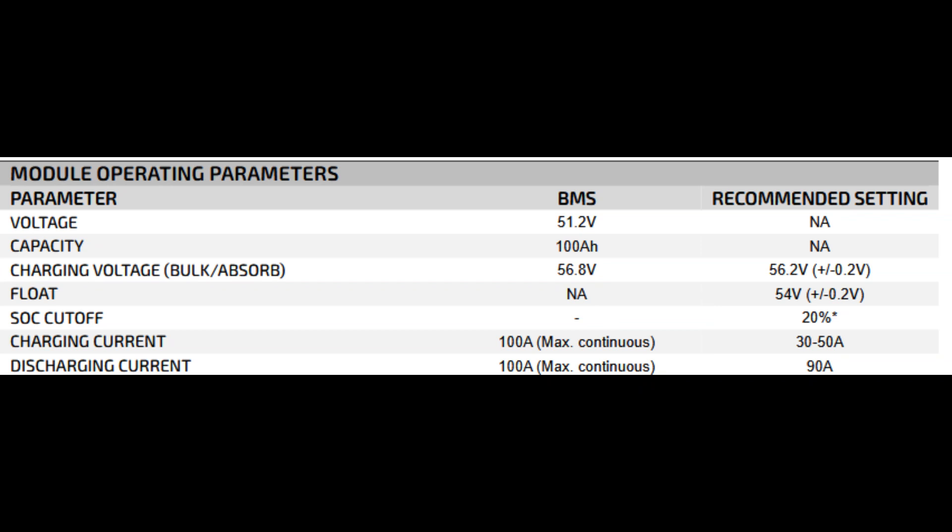Module operating parameters: voltage 51.2 volts, capacity 100 amp hours, charging voltage bulk absorb 56.8 volts, float 54 volts, SOC cutoff 20% recommended, charging current 100 amps max recommended 30 to 50 amps, discharging current 100 amps max recommended 90 amps. These are nominally 51.2 volts because each battery is basically 16 lithium cells in series at 3.2 volts per cell. For charging, they recommend 56.8 volts for bulk or absorb. I set my inverter to about 56.4 to 56.6 volts, helping prolong battery life. They recommend cutting off around 20% state of charge to maintain longevity.